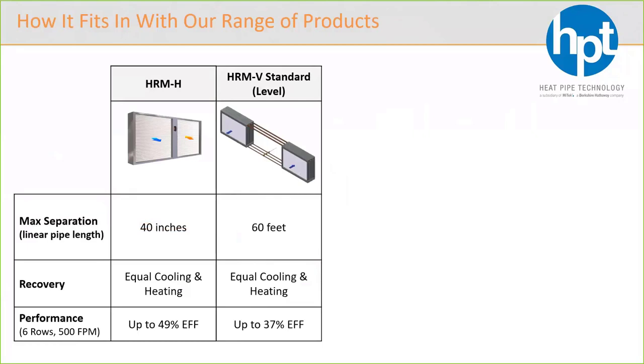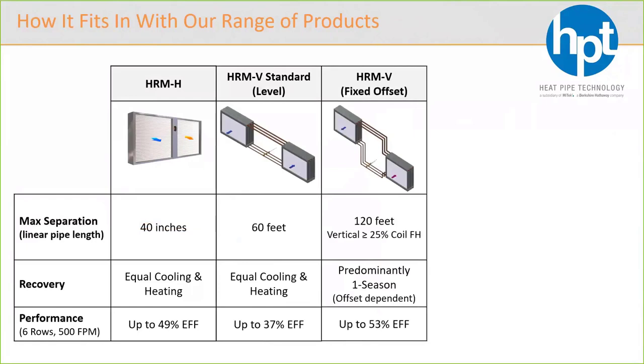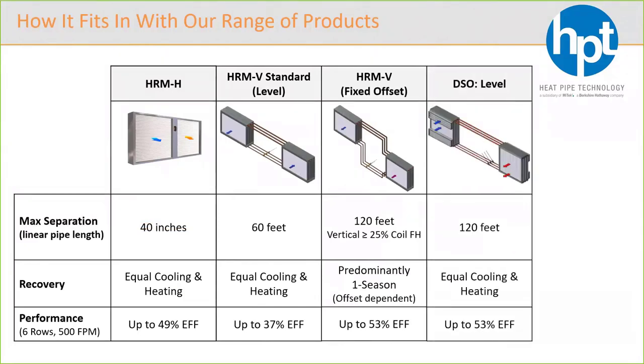However, the performance is not as good. So again, you can offset it and use gravity to help you get a little bit more performance. It also helps you get more separation. You see now it's increased to 120 feet. And there's another option within this range, which is called the DSO. And what we're doing is we're using dampers to control the airflow over the coil so you can get the benefit of an offset, but with the two-season recovery. And again, there's 120 feet.